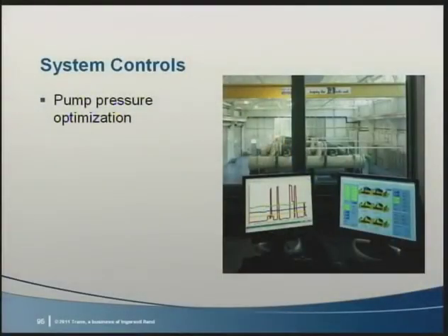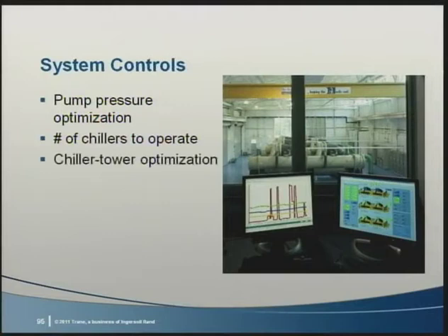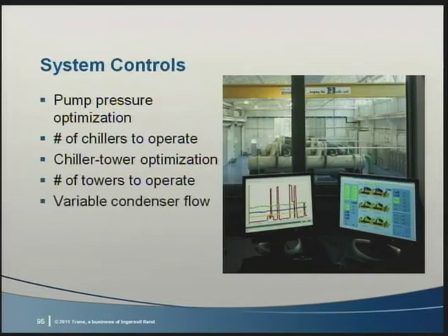For control retrofits, there are 5 topics we'll discuss today. The first one is pump pressure optimization, a new requirement of 90.1. Next is a question we get asked a lot: how many chillers should be operated? Then, how should the cooling tower be controlled to minimize chiller plus tower energy? We'll then go into the number of tower cells to operate and end our program today with a hot topic: variable condenser water flow. Okay, so the first one is pump control.